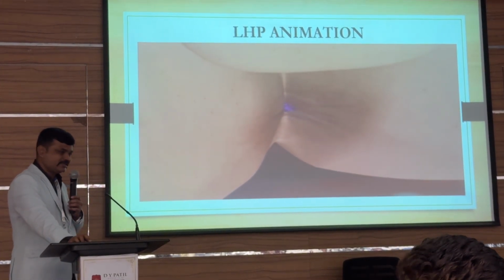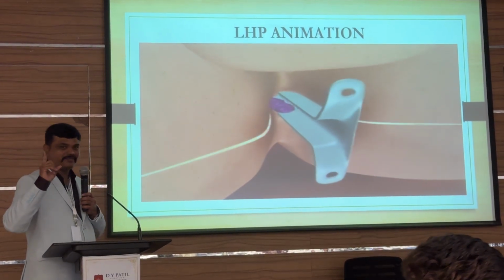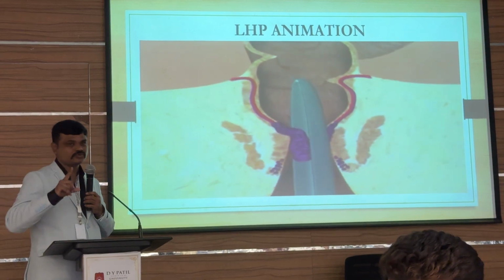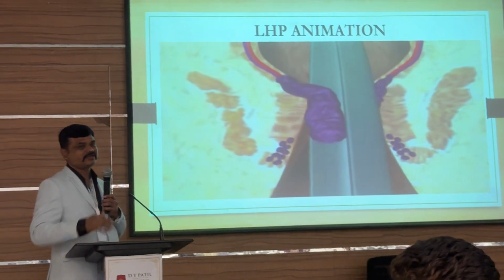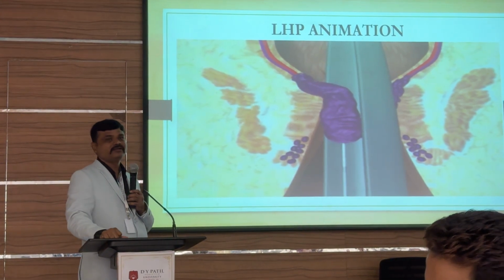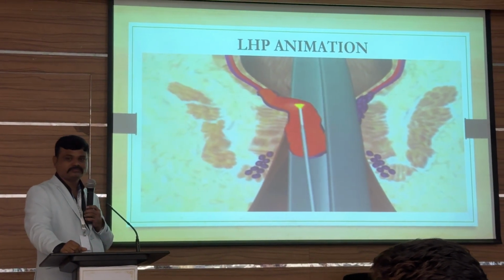So always use a slit proctoscope. Do not use a steel metal proctoscope while doing laser, because the laser can be emitted and transferred from the metal proctoscope. Always use a glass tip or fiber proctoscope.